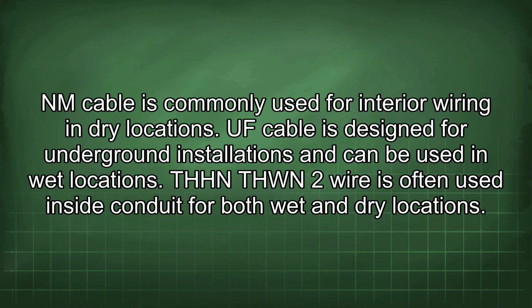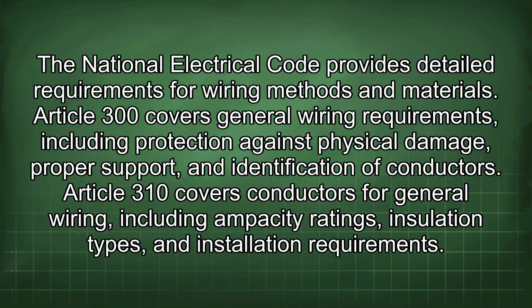NM cable is commonly used for interior wiring in dry locations. UF cable is designed for underground installations and can be used in wet locations. THHN and THWN-2 wire is often used inside conduit for both wet and dry locations. The National Electrical Code provides detailed requirements for wiring methods and materials. Article 300 covers general wiring requirements, including protection against physical damage, proper support, and identification of conductors. Article 310 covers conductors for general wiring, including ampacity ratings, insulation types, and installation requirements.